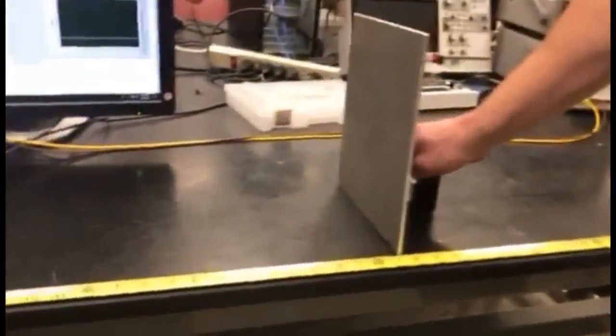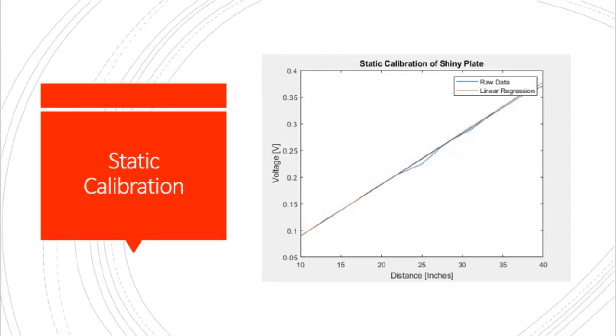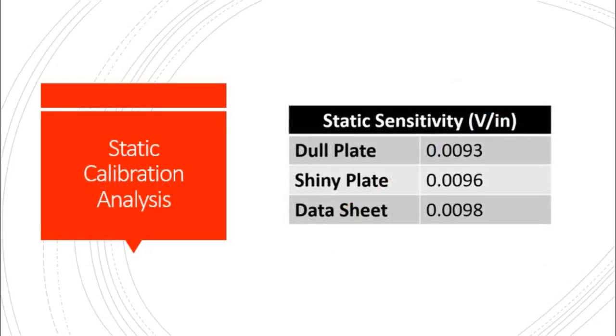Here's a short video of our static calibration. We took measurements every 3 inches from 10 to 40 inches. We found a linear relationship and used a linear regression to obtain the slope of this relationship, which we could then translate into the static sensitivity. Here are our tabulated static sensitivity values for the dull and shiny plate, as well as the nominal value given on the datasheet.